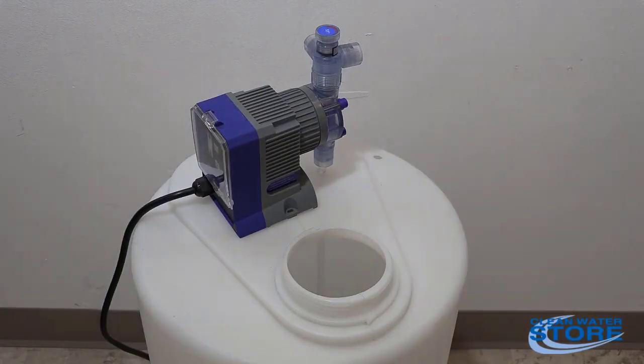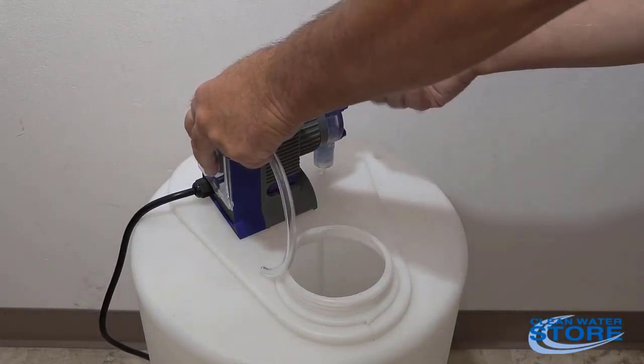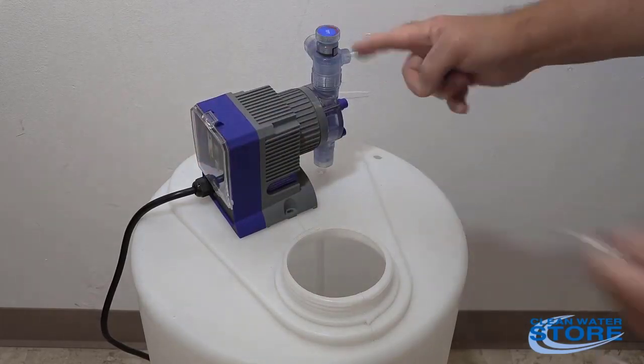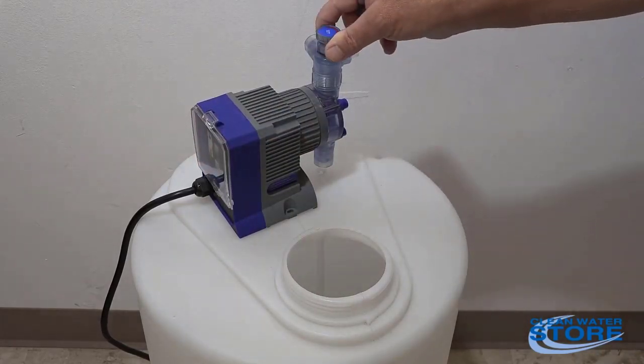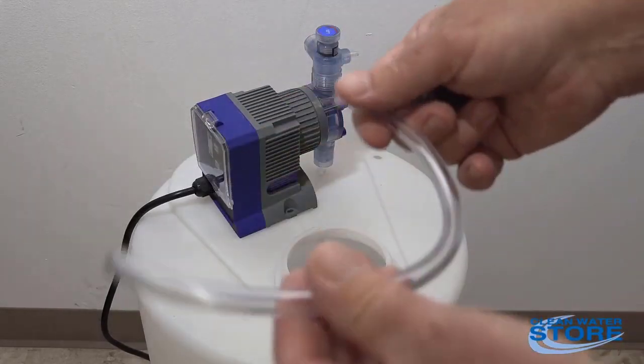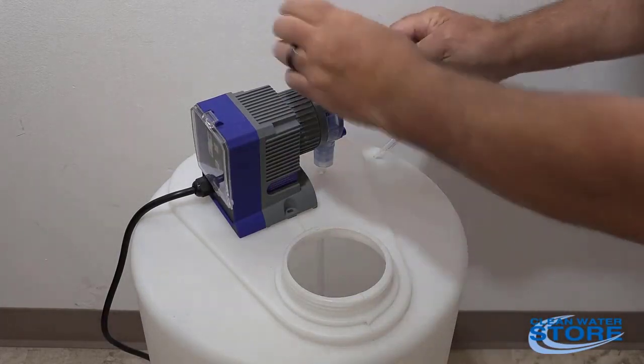Now we're going to hook up the tube to our kicker port. This kicker port here is used for priming the pump. Once we get the pump primed, you want to leave this cracked open slightly. It allows you to keep the pump primed all the time.